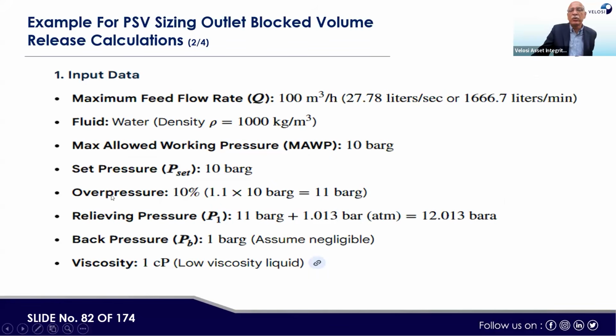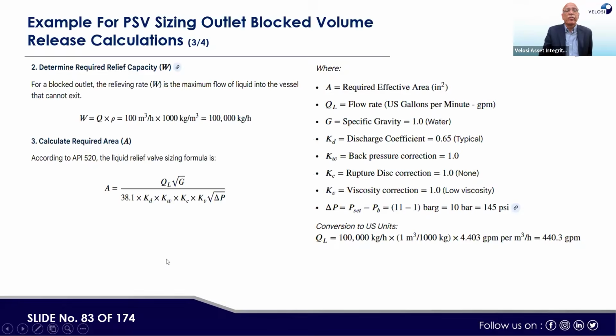Maximum feed flow rate, Q, let's say 100 cubic meter per hour. Fluid is water, density 1000 kg per meter cube. Maximum operating pressure, 10 bar, let's assume. This would be actual, we are assuming a scenario. Set pressure also 10 bar. Then overpressure means 10%, so 1.1, 11 bar. Relieving pressure would be 11 plus 1.013 atmospheric, 12.013 bar A. Back pressure 1 bar, assumed negligible. Viscosity 1 cP.